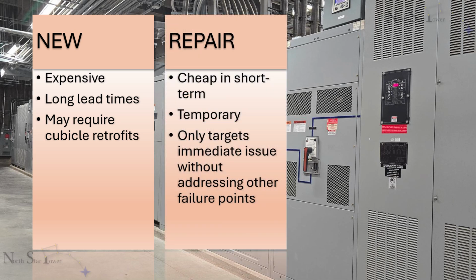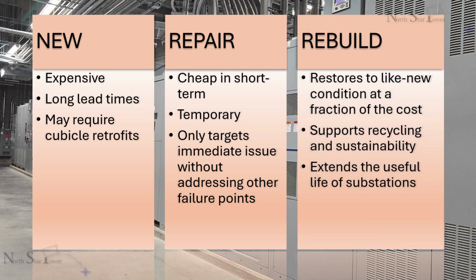The second option is to have the breaker repaired. This is a quick and cheap means of keeping substations running, but it only targets the immediate problem and doesn't provide a cover-all solution for other components that are wearing out. The third, and in many cases best option, is to have the breaker professionally rebuilt. Rebuilding restores the breaker to like-new condition at a fraction of the cost of replacement.